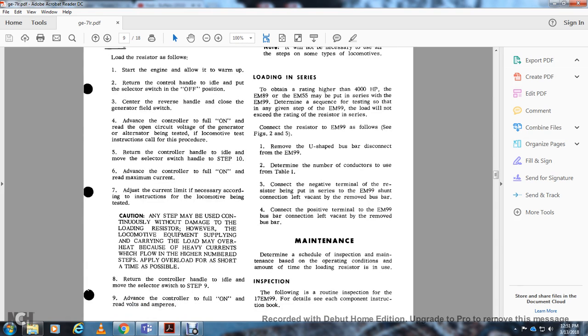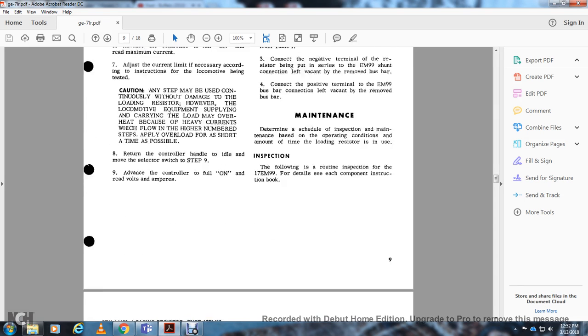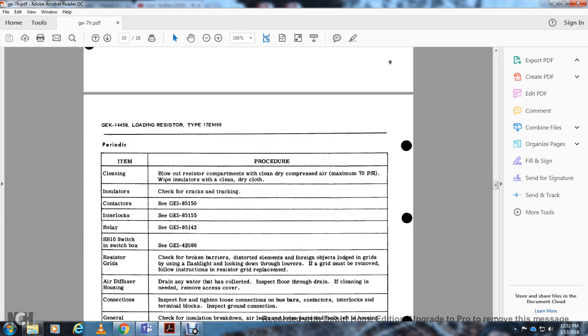Maintenance. Determine the schedule of inspection and maintenance based on the operational condition and the amount of time the loading resistor is in use. Inspection: perform the following routine inspection for the EM99, with details in each component instruction book. Cleaning. Blow off the resistor compartment with clean, dry compressed air, maximum 70 psi. Wipe insulators with a clean, dry cloth. Insulators. Check for cracks and tracking. Contactor. GEI-85150.